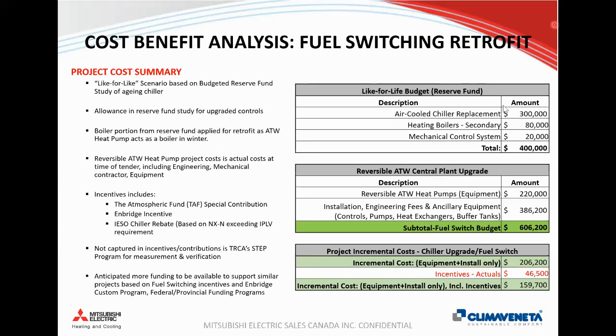So if we look at a like for like, and this is again per the reserve fund study, where there's essentially an allowance for certain capital costs throughout the life cycle of certain equipment that's planned. So in the reserve fund study for air-cooled chiller replacement, including labor, it was about $300,000 allocated for that. Heating boilers, there was $80,000 allocated for that.